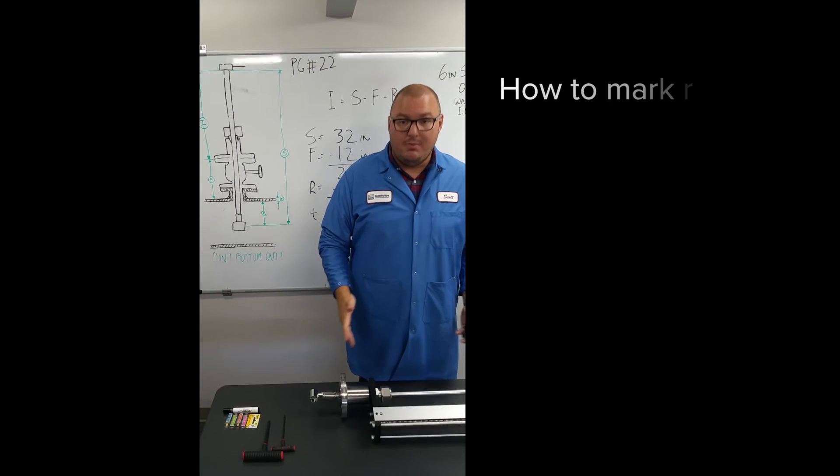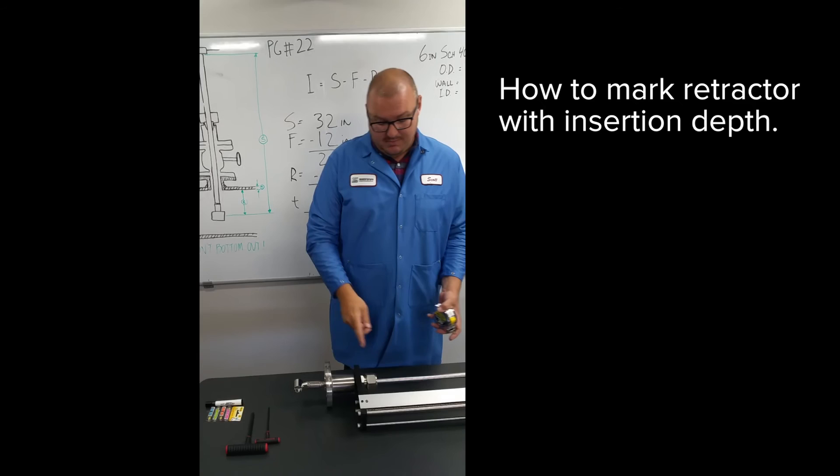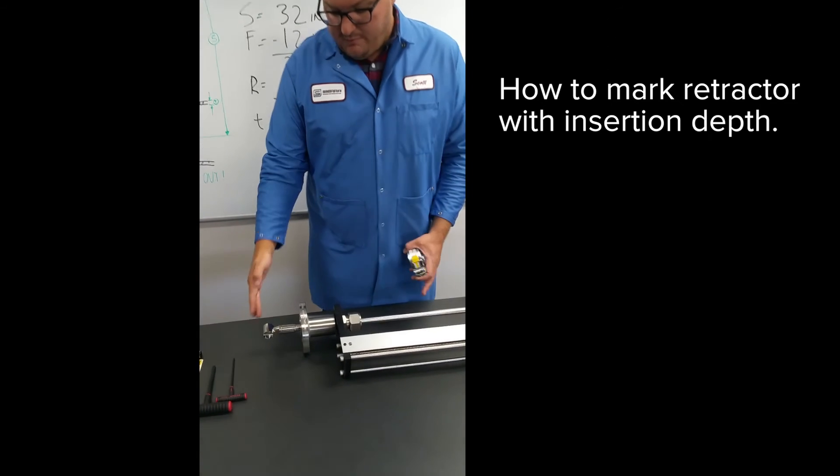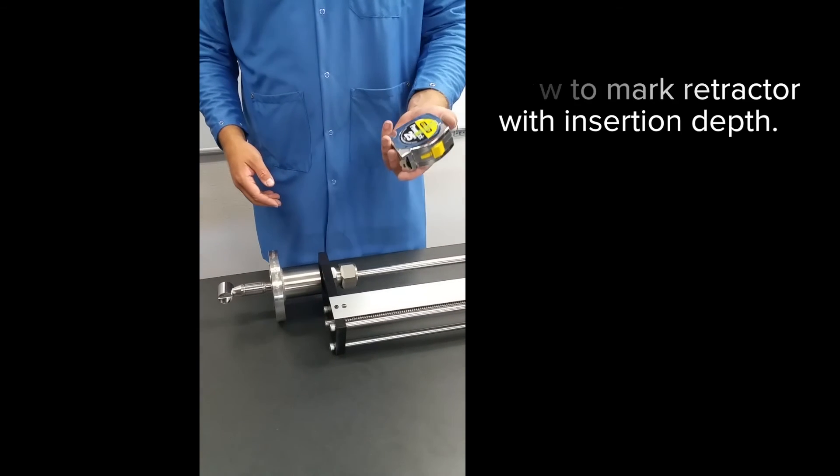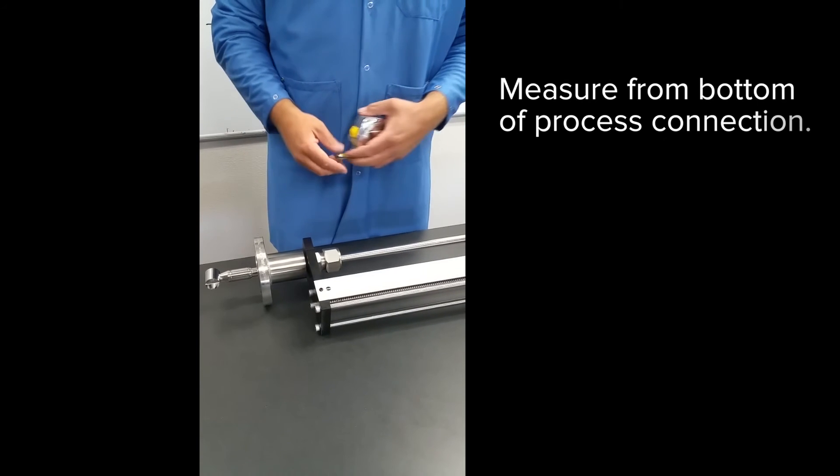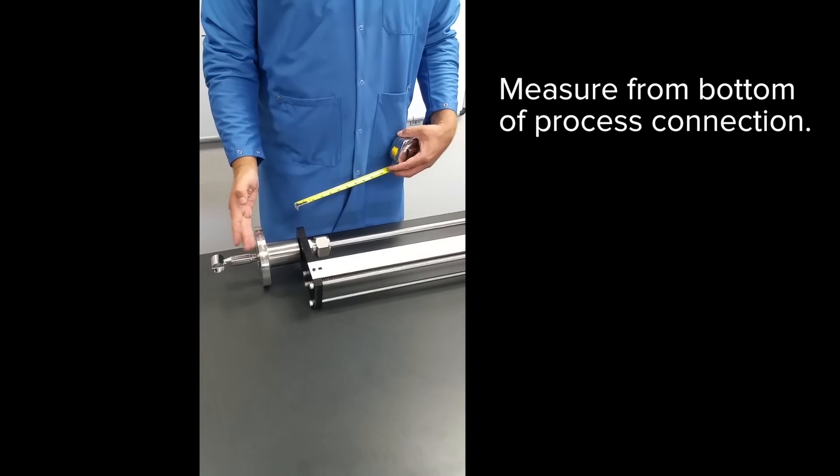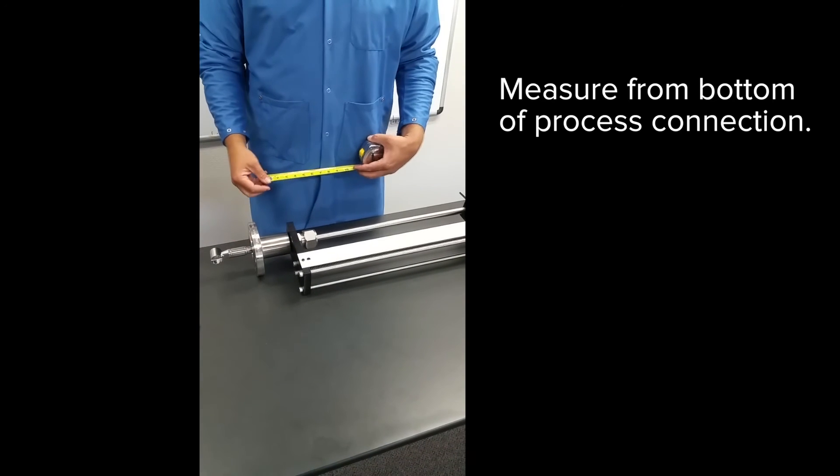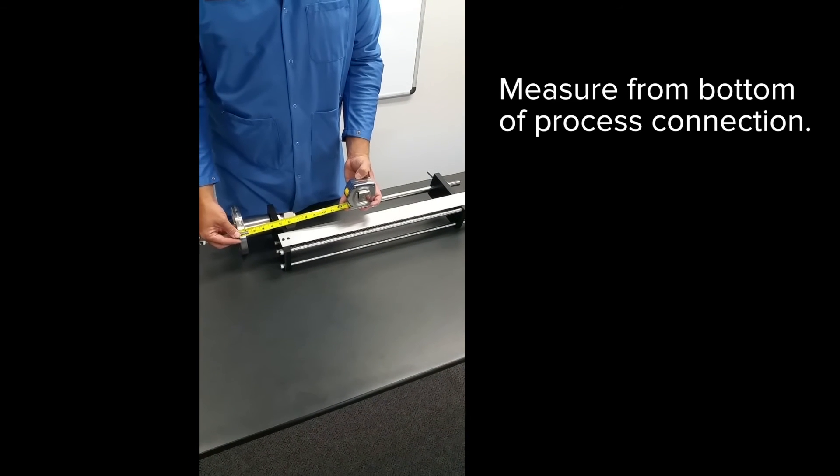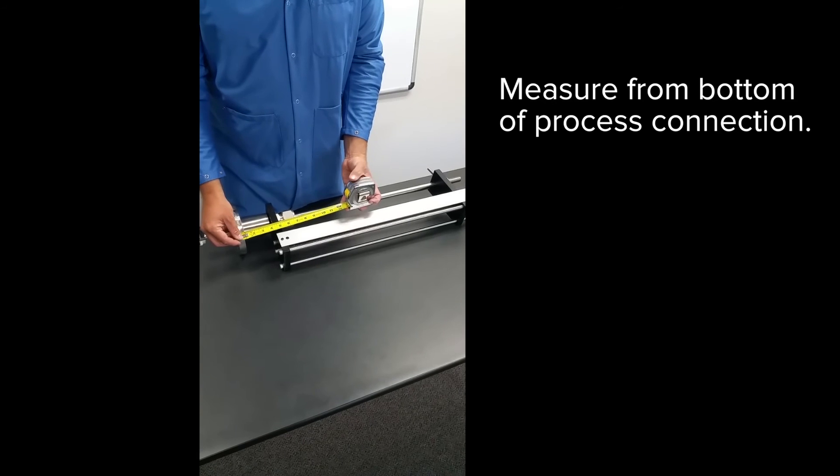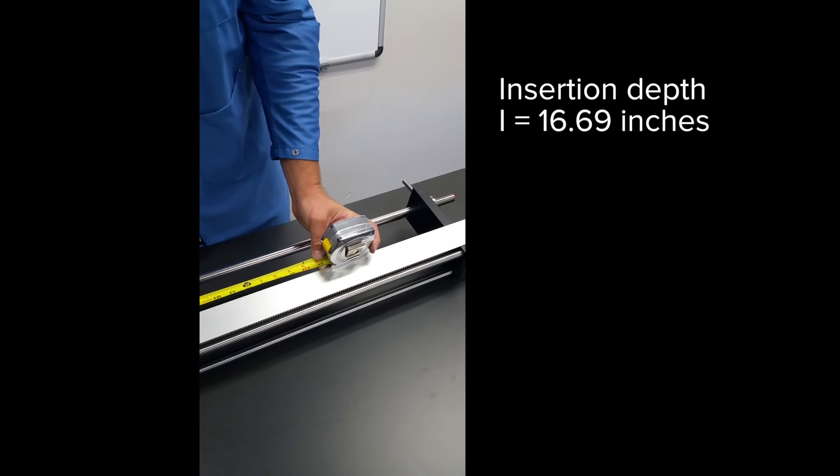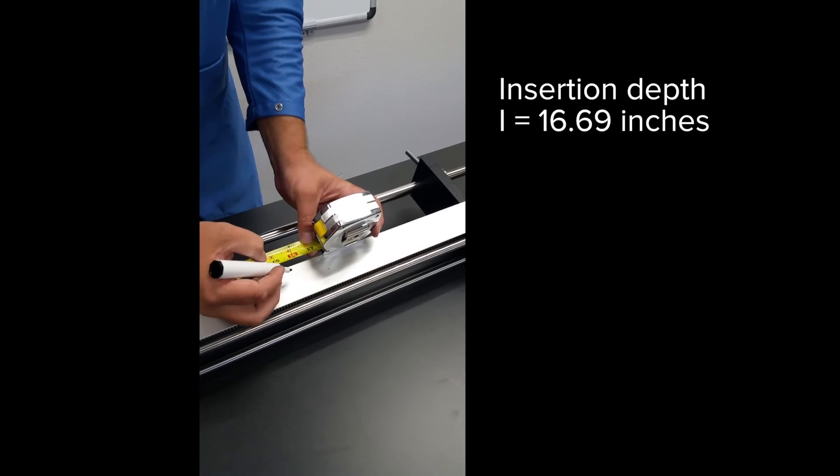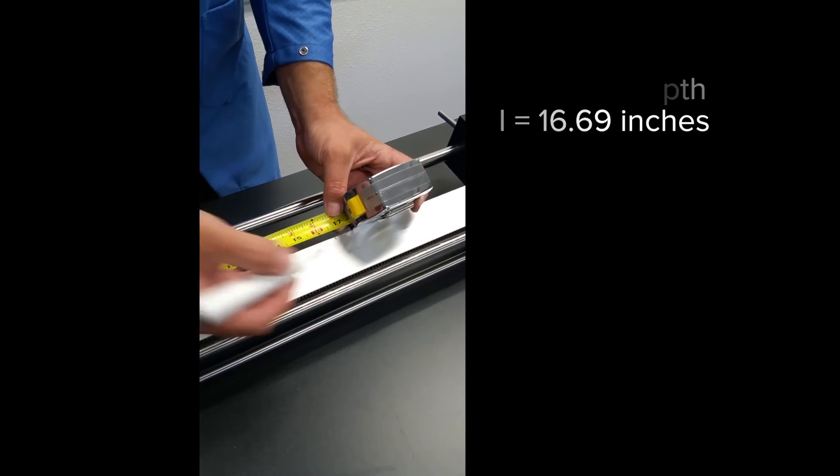Here, I have a mock-up of a probe and retractor to show you how we mark that insertion depth on the retractor. We've got a probe, process connection, and retractor. And I just have a tape measure. It's important when you're measuring, when you're going to mark the retractor for the insertion depth, to know that the measurement begins at the bottom of whatever your process connection is. In this case, we've got a flange process connection. So I just start my measurement here. I go up to my number, which is 16.69, and I'm just going to make a little mark there.